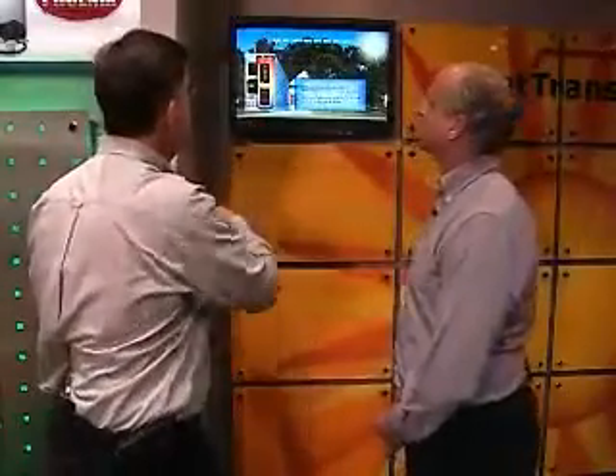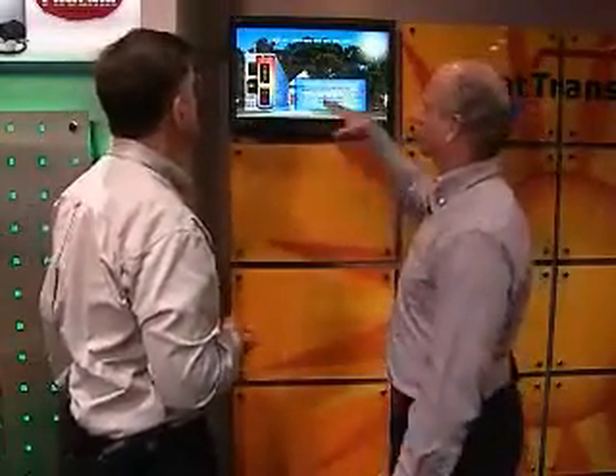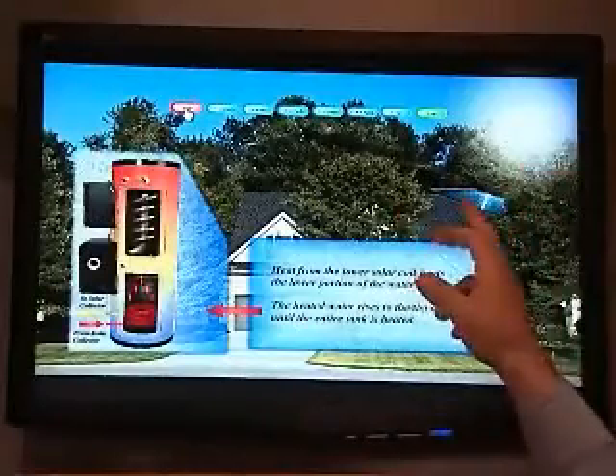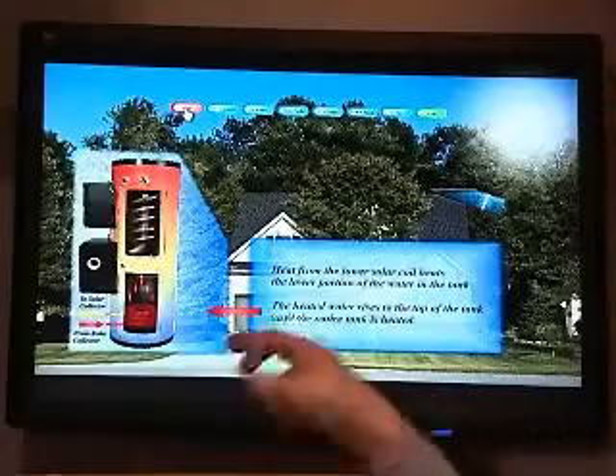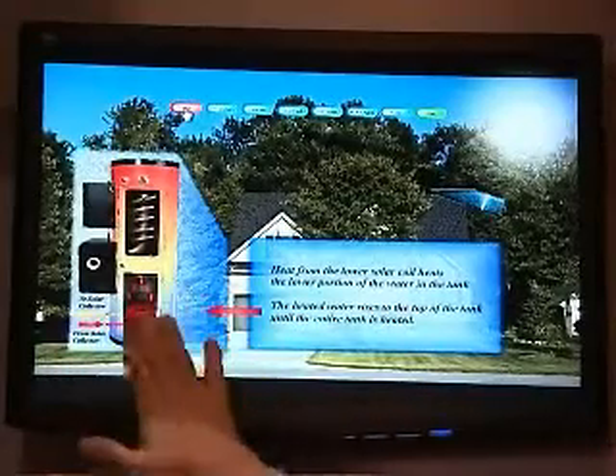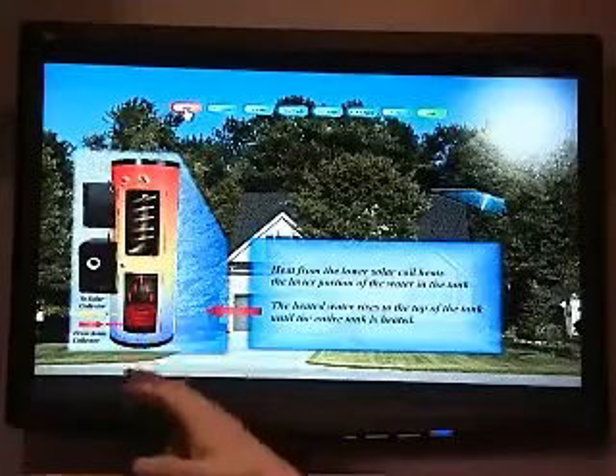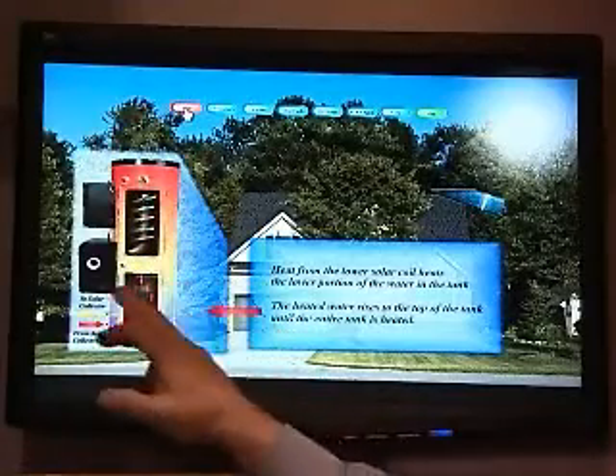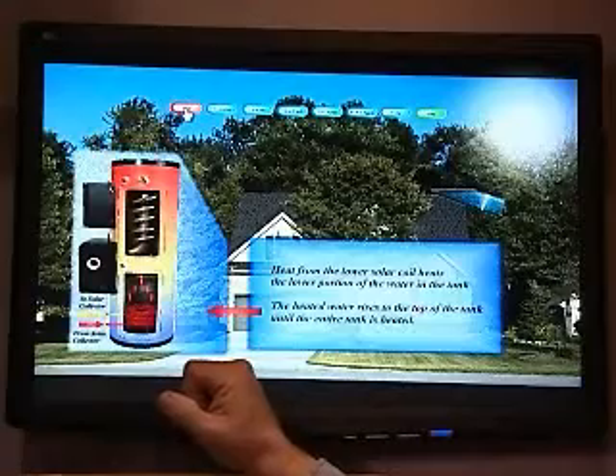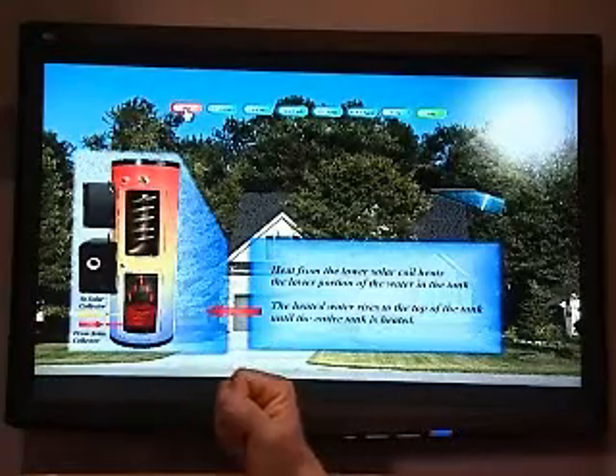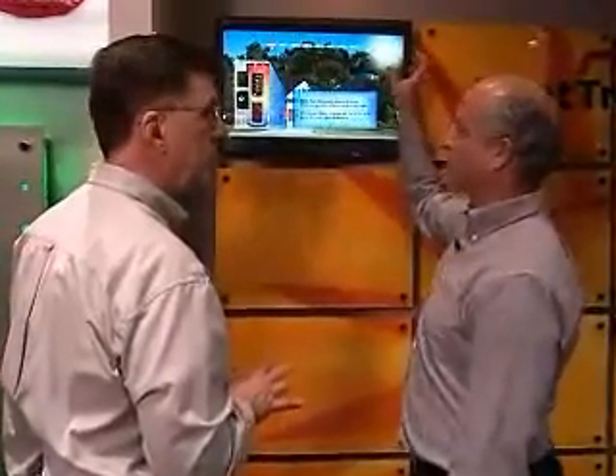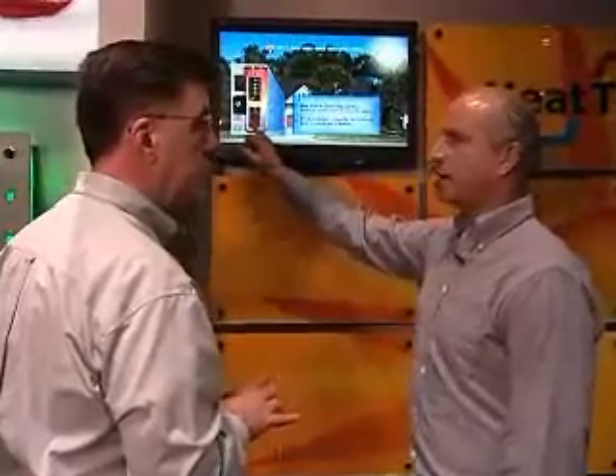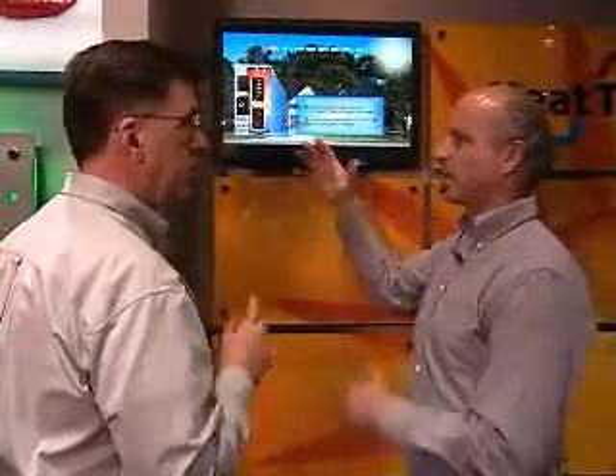I like this drawing. Yeah, this really depicts what we're doing. It gives you a good illustration. You've got obviously a sun here, and your solar panel. What we're showing is the heat collecting the energy from the sun, being transferred through this heat exchanger on the bottom of the tank. You can see the arrows. We're pushing that heat to the top of the tank. The main objective, again, is to keep the burner off. Then we've got our space heating heat pack that can backfeed to the system. We want to keep that 96% high efficiency burner off at all costs. That's the whole point of the system: let the sun use that energy, put it into the tank, put it into the living space, and provide domestic hot water. One simple package.